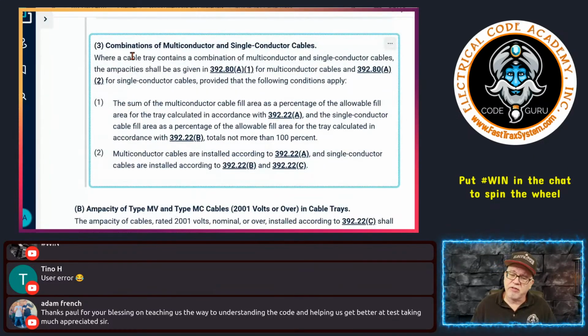And the last one down here is basically when you have multi-conductor cables and single conductor cables in the same cable tray, assuming they have the same voltage rating and all that kind of stuff. All this is saying is you calculate the ampacities for the multi-conductor cables one way. You calculate the ampacity for the single insulated conductors or single conductor cables another way, okay? And then when it comes to how they go in the same tray, you do the fill requirements for the single conductor cables and the fill requirements for the multi-conductor cables, and you have to make sure that combined, the fill requirement does not exceed 100%. So 50% of the fill for a tray could be made up of multi-conductor cables, and the other 50% is made up of single insulated conductors or single conductor cables. Combined, they can't exceed 100% of the fill.